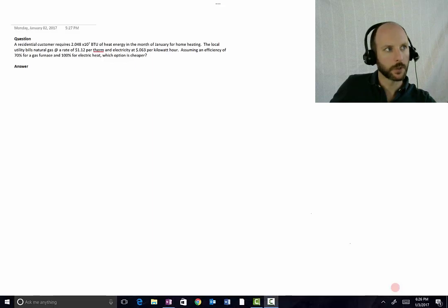1.2.3, a residential customer requires 2.048 times 10 to the 7th British thermal units of heat energy, or BTU, of heat energy in the month of January for home heating. The local utility will provide him natural gas at a rate of $1.12 per therm or electricity at 6.3 cents per kilowatt hour. Assuming that the gas furnace is 70% efficient in energy conversion and the electric heating element is 100% efficient, you are asked to determine which option is cheaper for that residential customer.